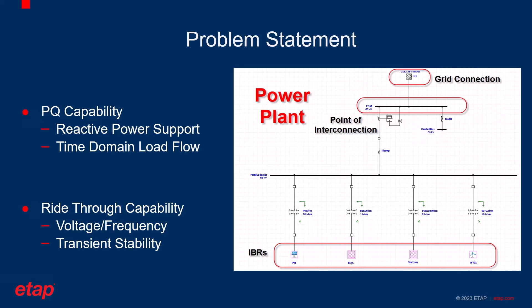Utilities also have requirements on ride-through capabilities of IBRs and power plants, meaning that in case of a voltage or frequency event, the inverter has to be capable of supporting a sufficient amount of reactive power to maintain the voltage at its neighboring buses and prevent unwanted trippings. These criteria — including the time the inverter needs to maintain voltage and support reactive power, as well as the voltage level or frequency — are all mandated as part of the grid code studies.